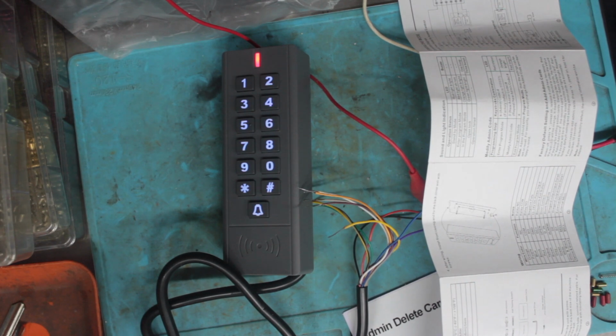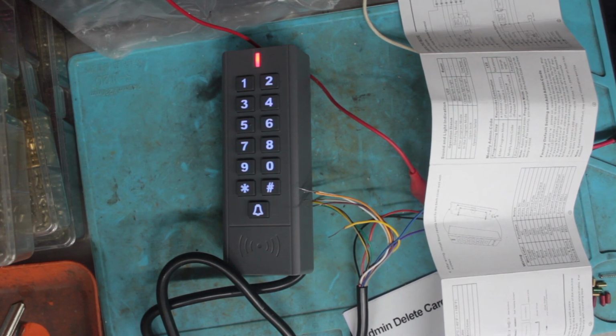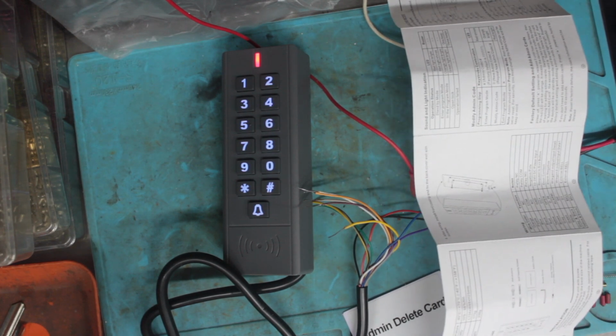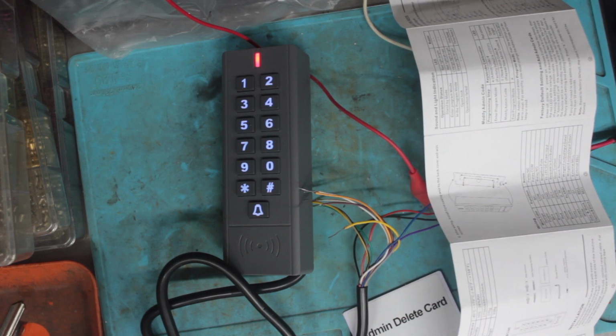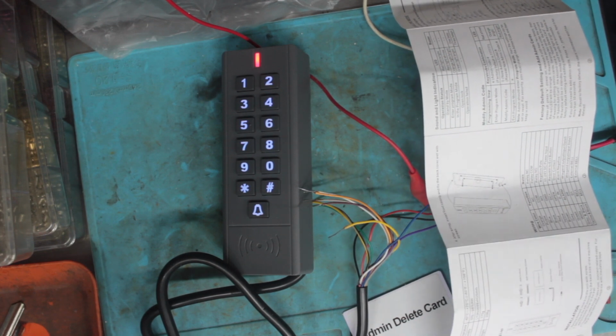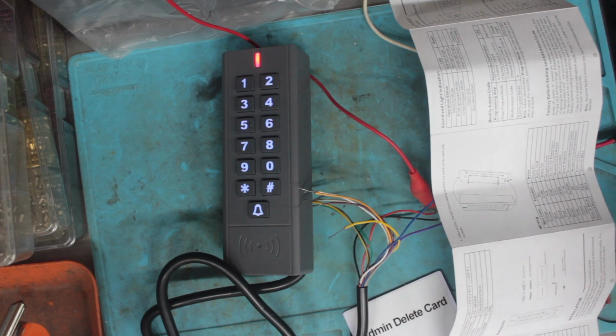Mounting is very simple. You just take it off, 2 screws through the back, screws are included with it. Amperage for your powered device is, I think, 3 amps. So your maximum load you would draw through this particular unit is 3 amps at 12 volt DC, as an example. Power voltage is 10 to 24 volt DC, not AC. So that just simply means that you can add it to a couple of different systems if you wish.